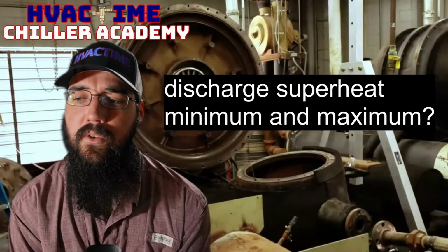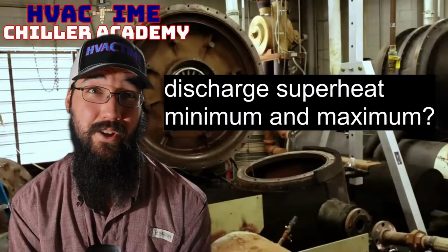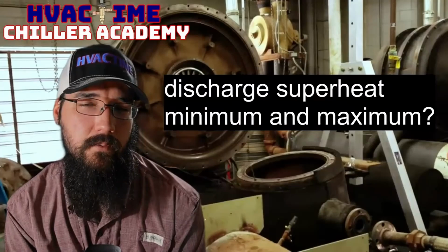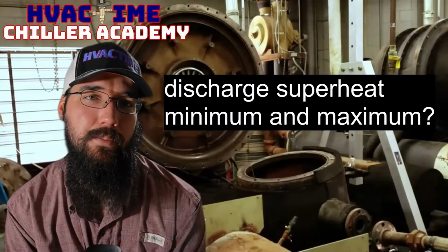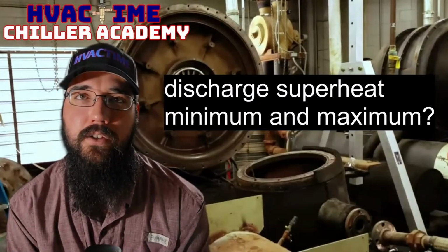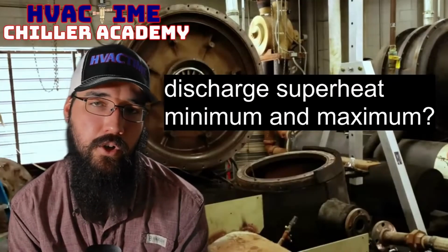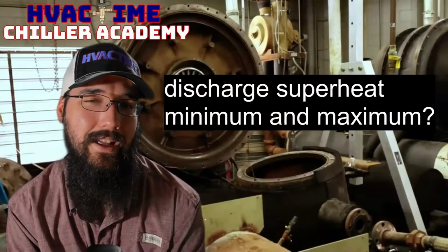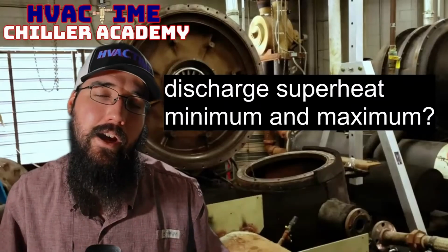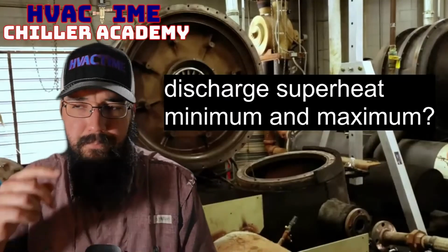Now, the dangerous parts of it. So the 30 degrees: there are some situations, especially at really high peak loads, where you might see more than 30. For a lot of compressors, it's probably not going to be that big a deal, especially if you have that high load. So just because you're over 30 doesn't necessarily mean freak out, or start diving in and chasing ghosts that aren't really there. That's the big thing that gets a lot of us. We start chasing ghosts, trying to see what's going on, when in reality everything's fine. It's just a specific circumstance, right?